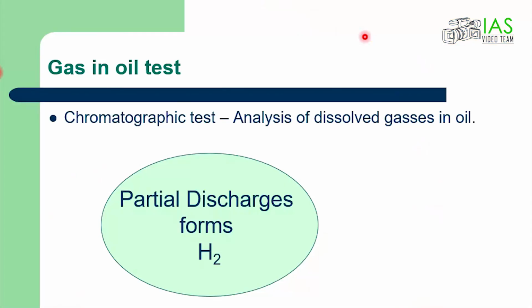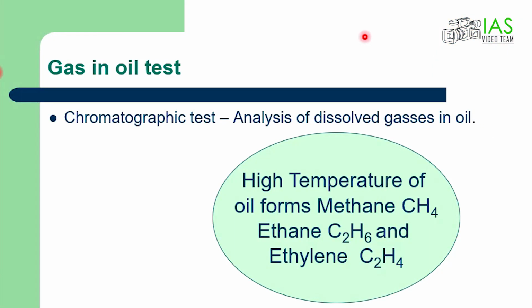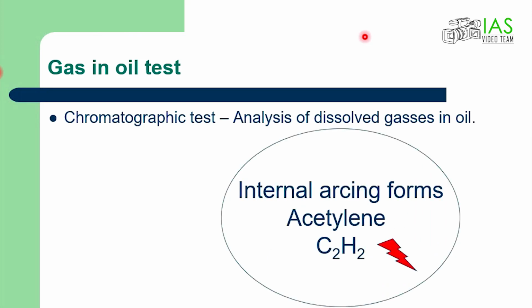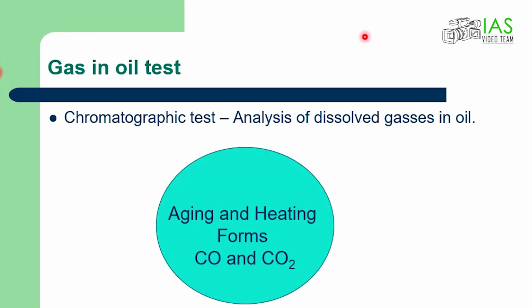Gas in oil test. Partial discharges form H2. If you have partial discharges within the transformer, it forms hydrogen. And high temperatures of oil form methane, ethane and ethylene, hydrocarbons, right? And internal arcing forms acetylene. So you can test these contents of gases in transformer oil. Aging and heating form CO and CO2.